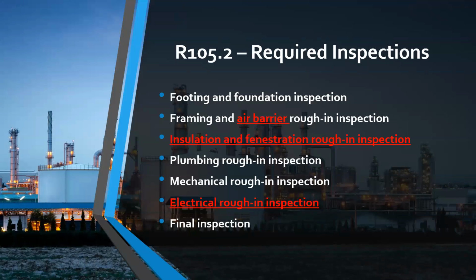Required inspections. This is one where I've talked about before that some cities are already taking advantage of this and moving it into their 2021 adoption. But as you can see, everything in red here was added to this. What they did was split the air barrier and insulation inspection in two, and now one of them is framing and air barrier rough-in inspection. Then there's an insulation and fenestration rough-in inspection. Then they also added an electrical rough-in inspection, because that deals with the renewables and the solar and the conduit all the way back to the panel. It looks at that part of it.